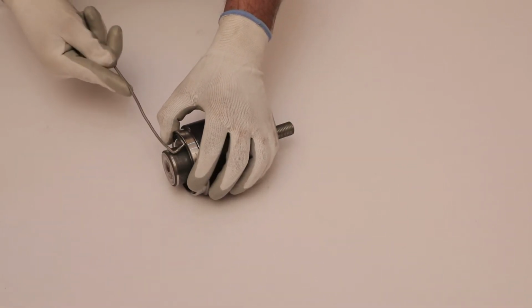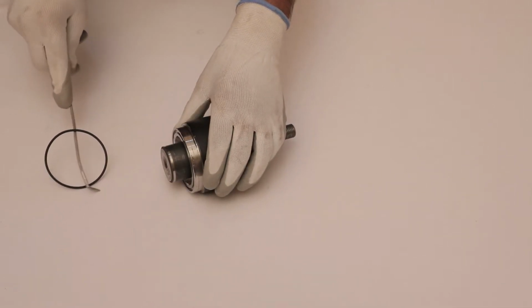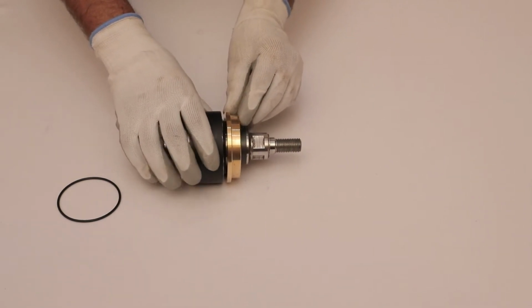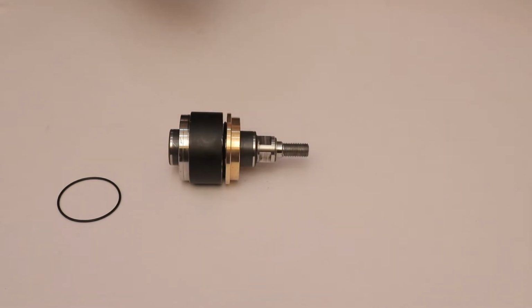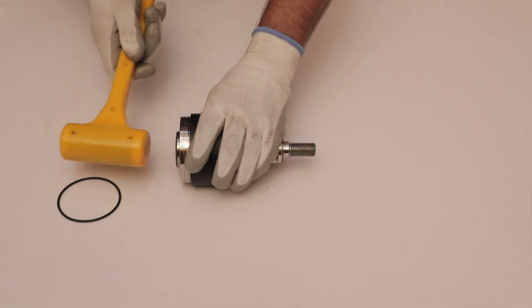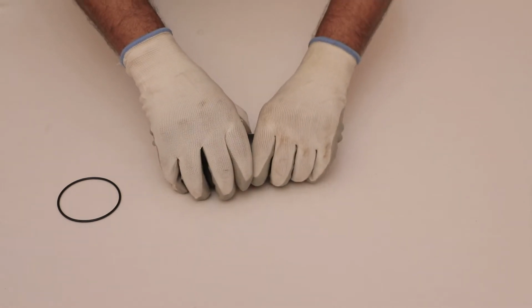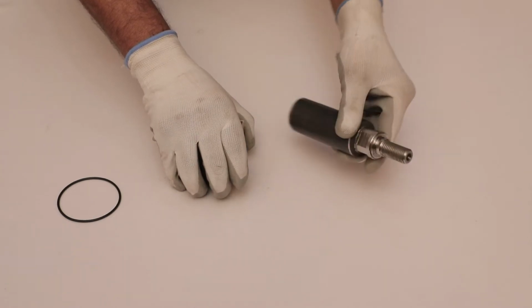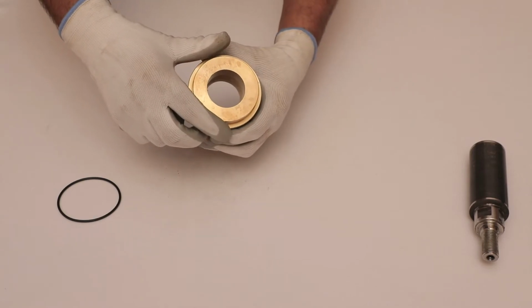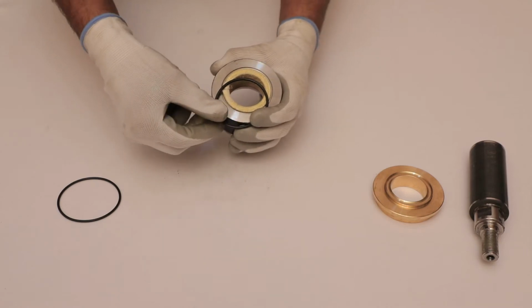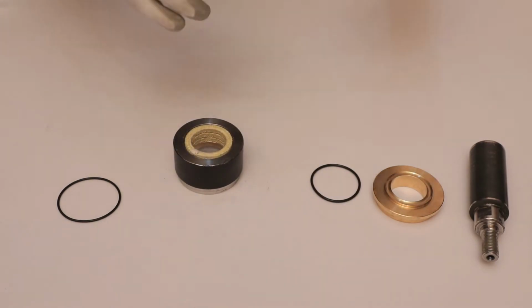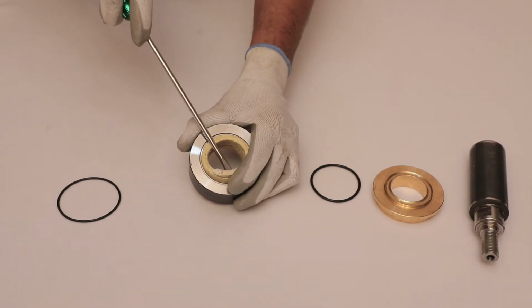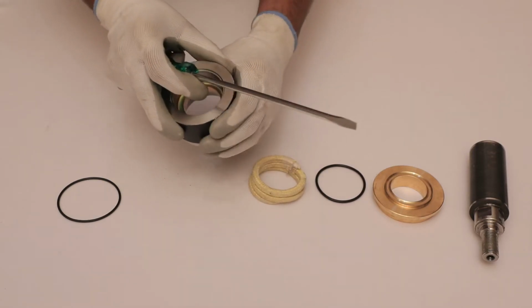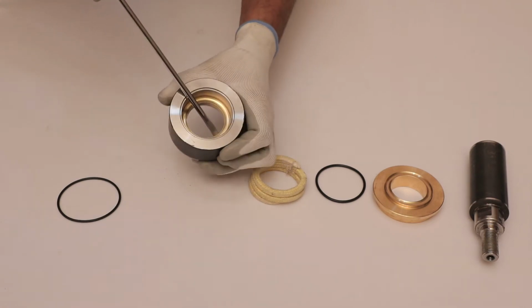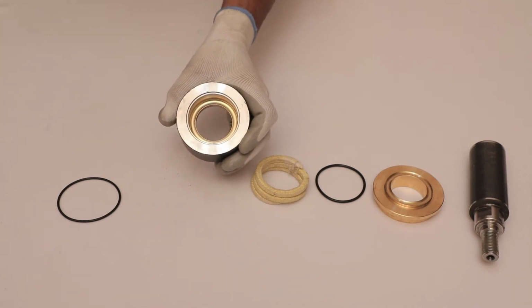Disassembly of stuffing box assembly parts. First of all, with the help of pick, remove the O-ring from the stuffing box. Now pull out ceramic coating plunger manually. If it was stuck in a stuffing box, then gently push it with a rubber hammer from the opposite side. After that, remove the outer support ring and O-ring manually. With the help of screwdriver, remove the plunger seal. And then pull out the inner support ring manually.